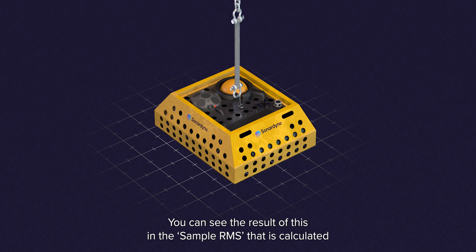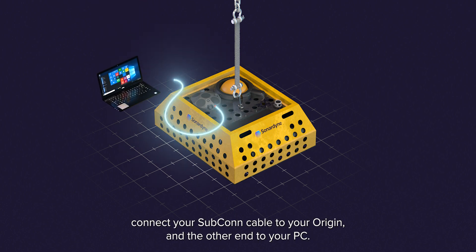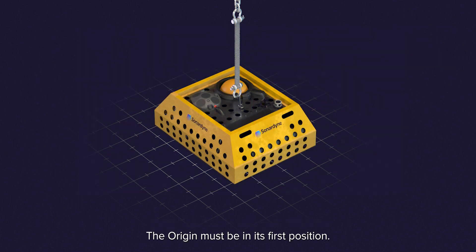You can see the result of this in the sample RMS that is calculated once the calibration is finished. Once your frame is ready, connect your SubConn cable to your Origin and the other end to your PC. Details of how to do this are in the Origin 600 manual. Once connected to Origin, open the web UI and navigate to the settings page. In the bottom right hand corner, you'll see the calibration area. The Origin must be in its first position, tilted so that the side which is forward is up in the air. Once we are in this position and steady, we can press start.